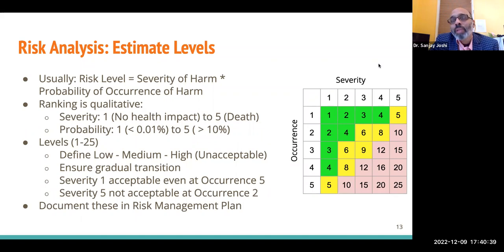Your energy hazard is probably going to be low, but the functionality hazard: what if the device fails? If it doesn't detect correctly, or it tells the woman that she's pregnant when in fact she is not, and the other way, it says that the woman is not pregnant when in fact she is. Now you always have to think about the harm that could happen, right?